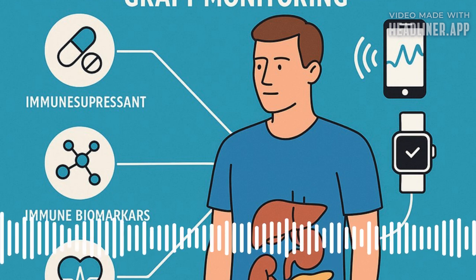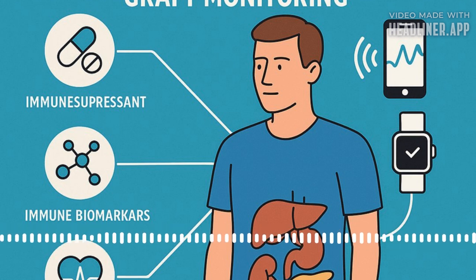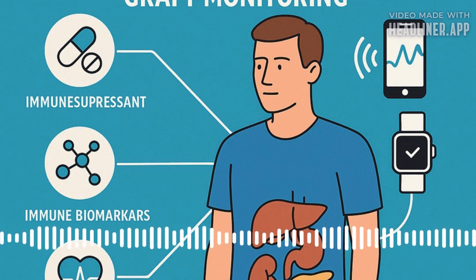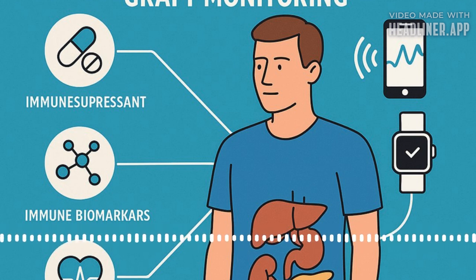Okay. What else? Accuracy must be a big one. Huge. We touched on this with sweat versus blood. Readings from these surrogate fluids, sweat or ISF, might not perfectly match what's in the bloodstream. And lots of things can throw them off. Definitely. Your sweat rate changes, skin temperature fluctuates, other molecules in your sweat or ISF, like uric acid, even vitamin C, or changes in pH can interfere with the sensors and skew the results. So you need really careful calibration. Absolutely. And maybe even personalized conversion factors for each patient to translate, say, a sweat reading into a clinically meaningful blood equivalent value. It adds complexity.